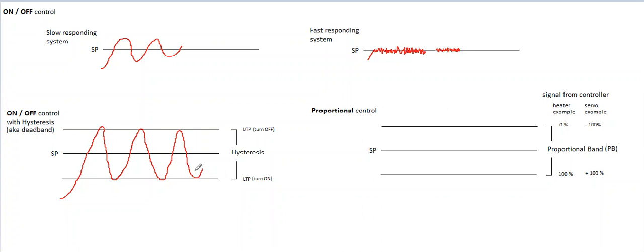And that's the trade-off, really. You're going to solve this rapid oscillation that can wear parts out. Yes, you're slowing it down. The system's going to have a slowed down response now, but you've done that at the cost of staying tight to the set point, however many degrees you wanted to add in either direction. So this method can hold the temperature to the set point plus or minus a certain amount of degrees.